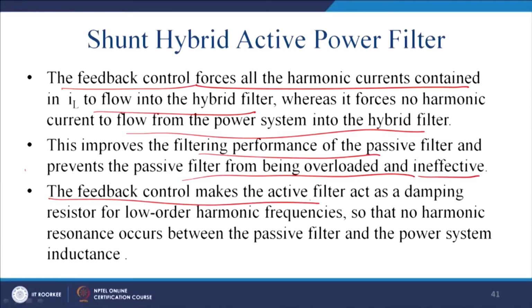And thus we require three kinds of control. First, let us talk about the feedback control. The feedback control makes the active power filter act as a damping resistor for the lower order harmonics, so that no harmonic resonance occurs between the passive filter and the power system inductance. So, this is how the active damping can be achieved by this feedback control.